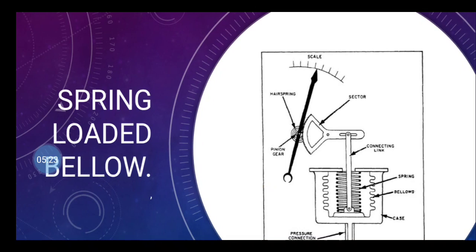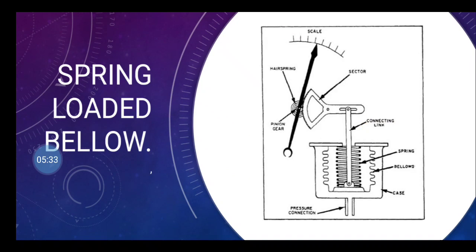It consists of a scale, spring, sector, pinion gear, bellows, pressure connection, connecting link and case. Okay, all these things are contained in the spring loaded bellows. In this type, pressure is applied on one side of the bellow. The resulting deflection is counterbalanced by the spring. These bellows are very sensitive, so they are used in tripping devices and signaling devices.